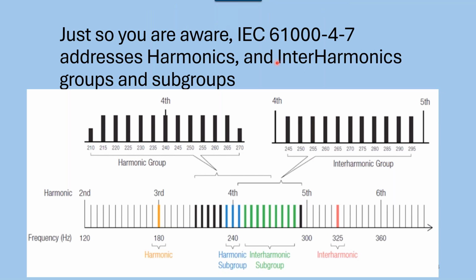There's also a thing, and they refer to IEC standard 61000-4-7, and this is just so you're aware of it, called interharmonics. These are all the harmonics that are between the normal harmonics. So here I've got the third, the fourth. Here are the interharmonics that are in between. And those are actually harmonics that could be created. And when we get into some analysis, we may need to actually go into the interharmonics and look at them. Okay? Any questions at this point?